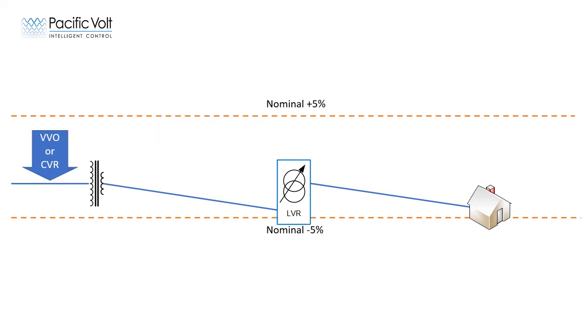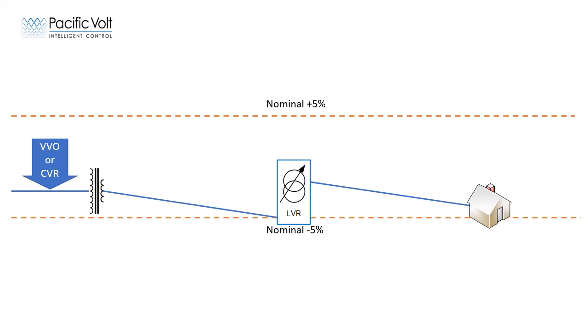The goal of CVR and volt-var optimization projects is to lower the voltage in order to reduce peak demand charges and/or reduce energy consumption. An LVR can be selectively applied to maintain the optimal voltage for customers which would otherwise drop below the minimum during high load periods. This allows for more reduction of the feeder voltage and therefore greater energy savings for these programs.